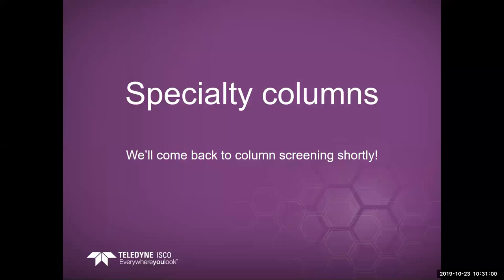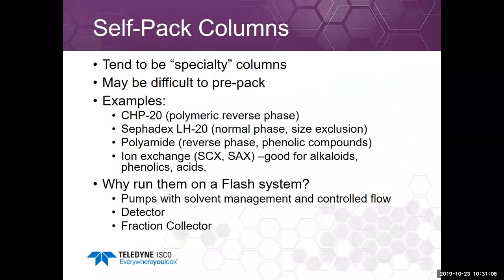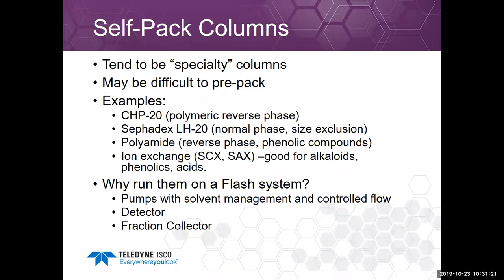I'll briefly discuss specialty columns and how you can use them for solvent screening. These tend to be specialty columns you have to pack yourself because they sometimes need to be pre-swollen with your solvent, making them difficult to prepack. CHP20 polymeric reverse phase is commonly used for natural products; it tends to swell slightly differently in water versus methanol, so it can't usually be prepacked. It also cannot be used for non-aqueous reverse phase — only water and methanol.